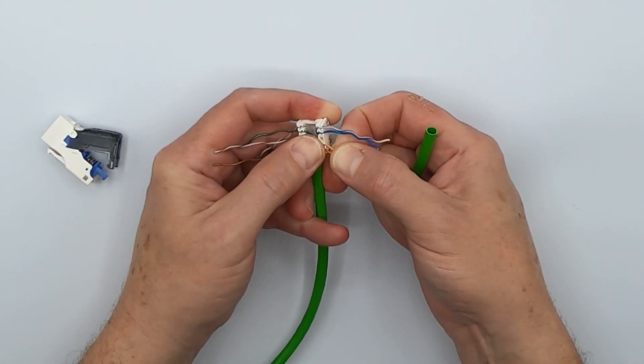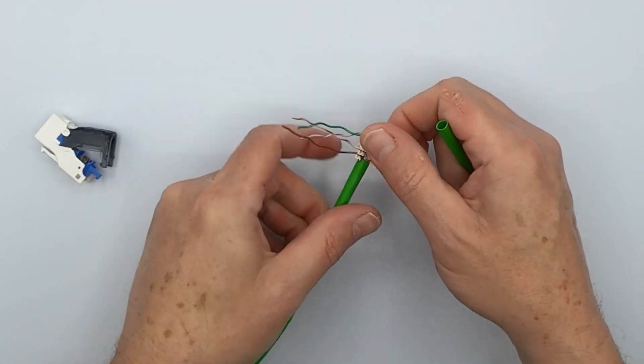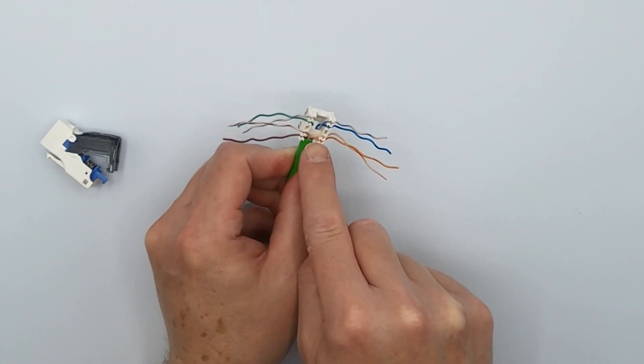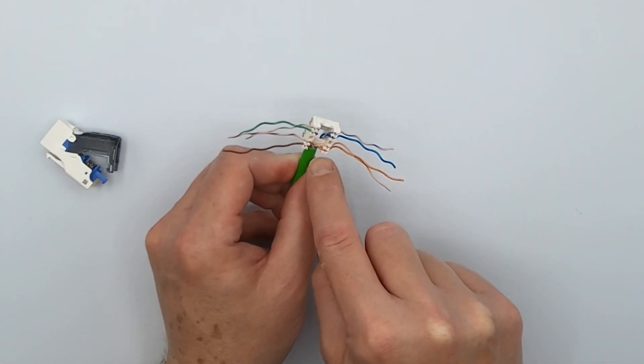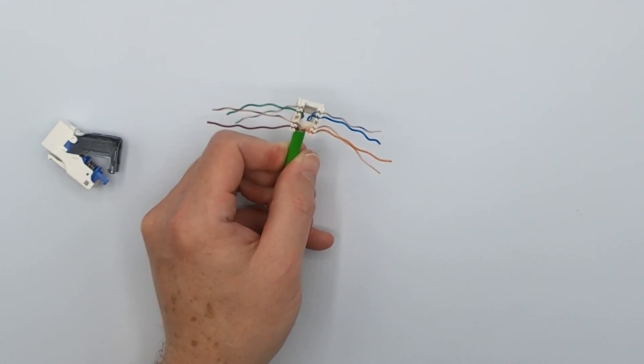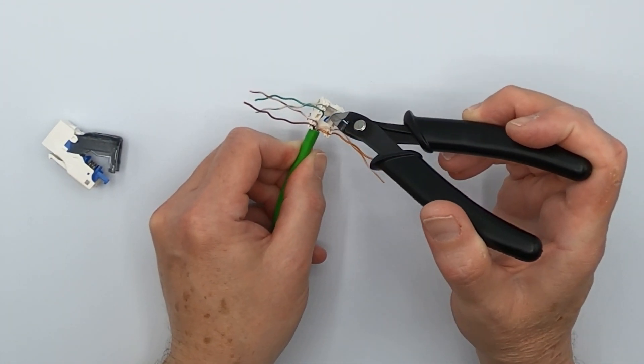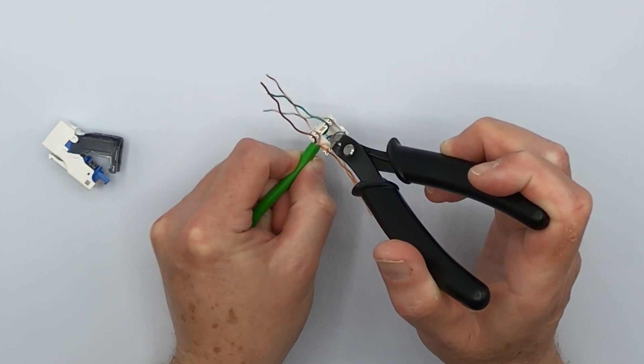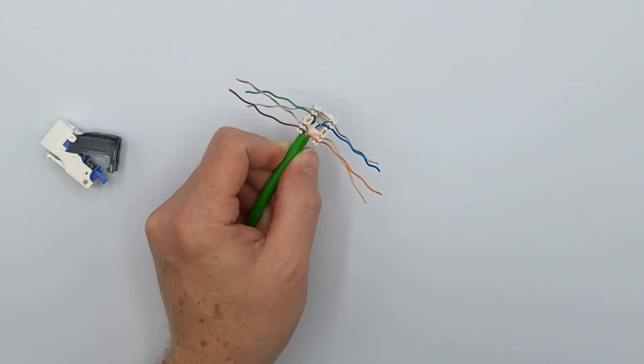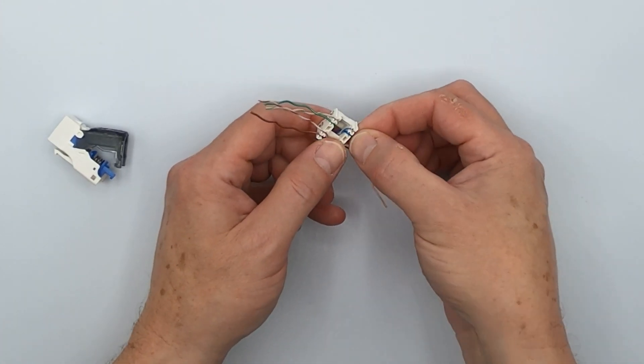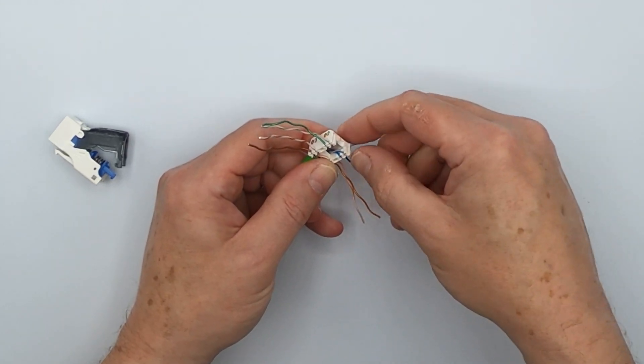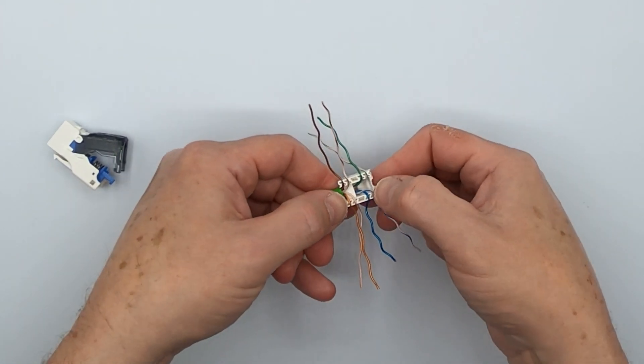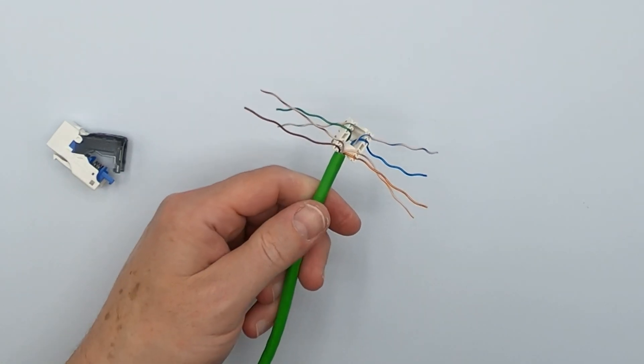Especially on these rear pairs if you like. Now again, they're still on spec. If I was to terminate it just like this, it would be fine because the distance from the last twist to where it's actually going to terminate here is going to be less than half inch, and it's going to be the case in all these pairs. Now one thing you do need to take a good close look at though is right after it gets threaded into the cap, always check the next pair or the next twist down. And there's an air gap in there. And if you can see it, you can see an air gap, you don't want that air gap because that's the same thing as if you had untwisted it. So what I would do is unseat it, pull again tightly, and play with it until you actually do get that air gap out of there. And we successfully got the air gap out.